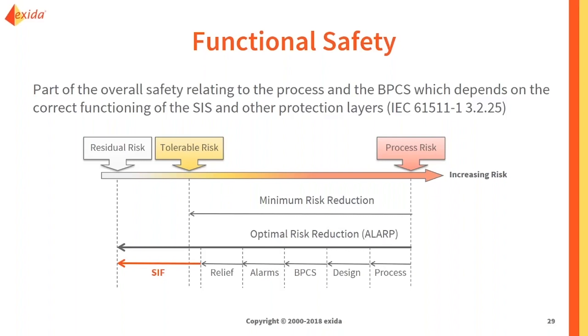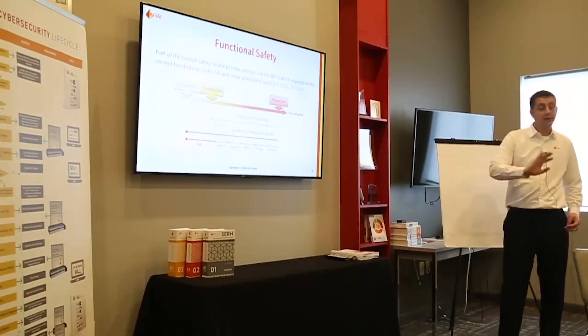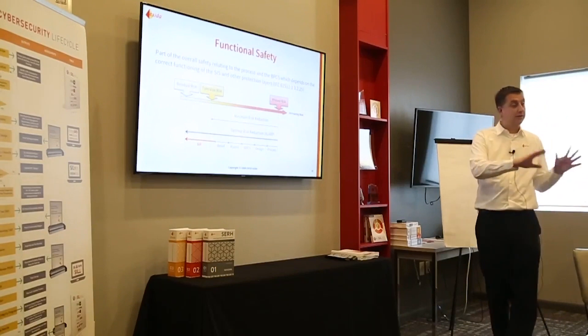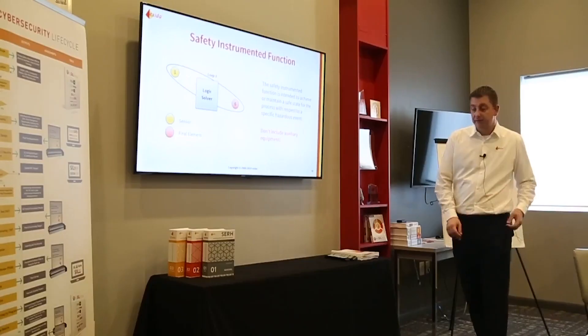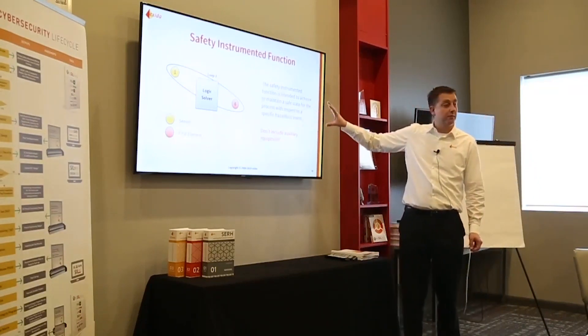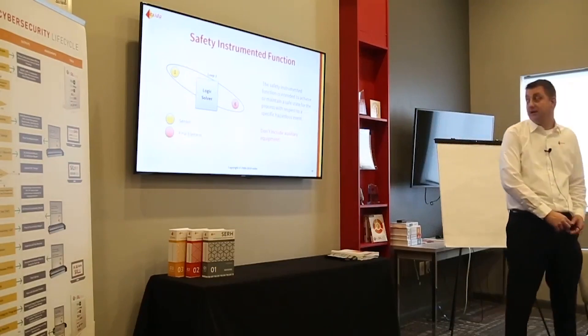As you can see from the graph, if the risk reduction from other layers would be just a little bit larger, we wouldn't need a safety instrumented function at all. So I'm not advocating that we should always use safety instrumented functions, even though that's what we'll focus on. A safety instrumented function needs to detect the hazard and bring the process to a safe state — it is expected to achieve or maintain a safe state with regard to a specific hazardous event.